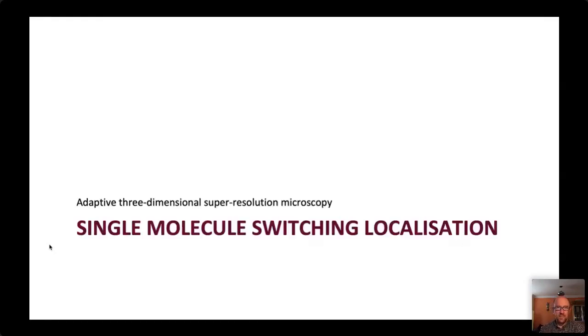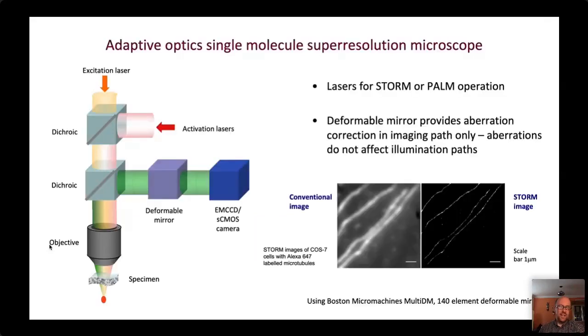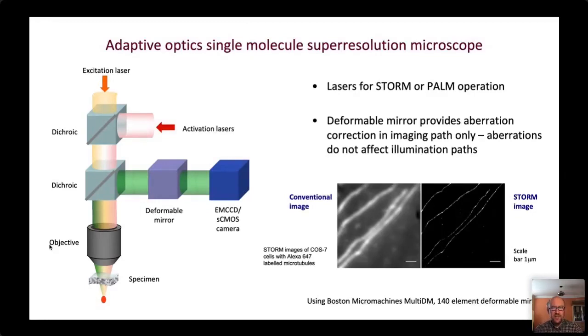In single-molecule switching localisation microscopy, the optical system uses a collection of lasers to illuminate the specimen and excite fluorescence, which passes back through the specimen, becomes aberrated by the specimen structure, then reflects off the deformable mirror onto the camera. The deformable mirror is used only in the emission path, as that is where aberrations matter — it doesn't affect the flood illumination path. Image formation involves acquiring tens of thousands or hundreds of thousands of blinking single-molecule images and reconstructing them into a super-resolution image showing far more detail than the conventional image.